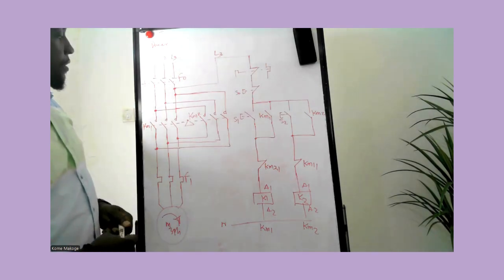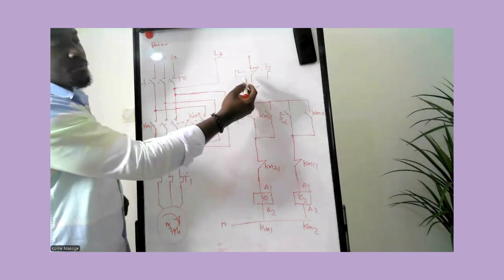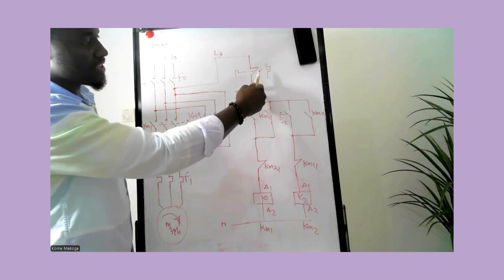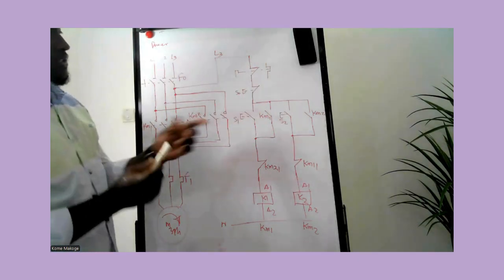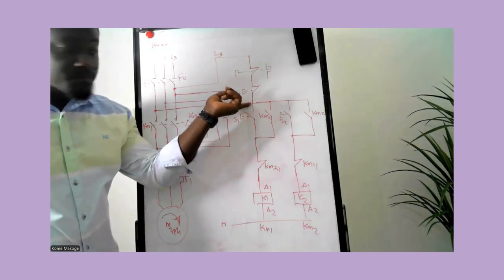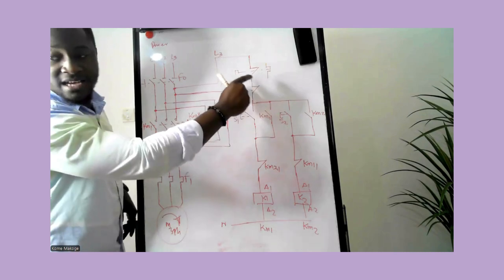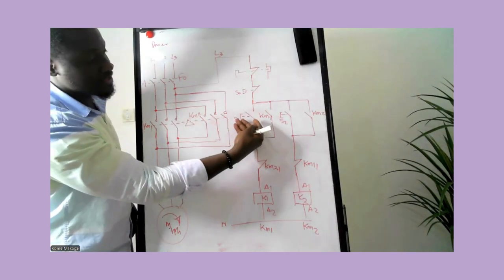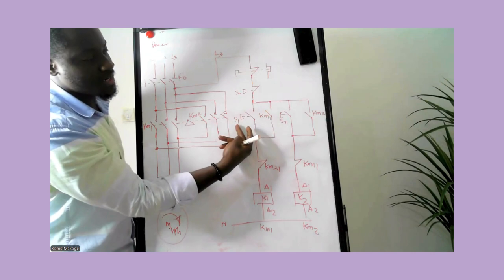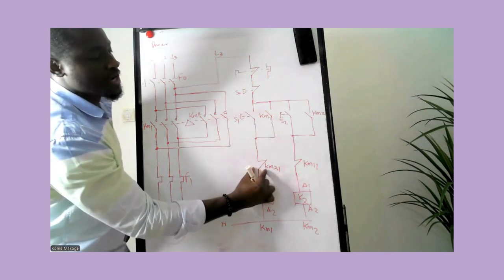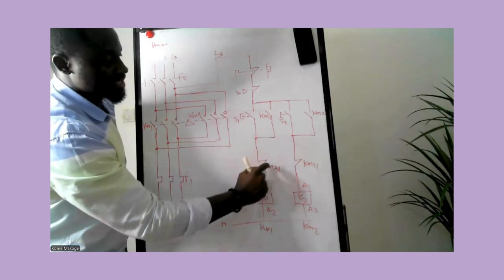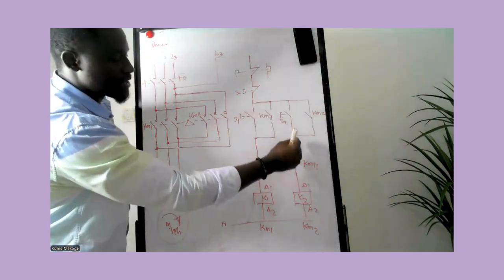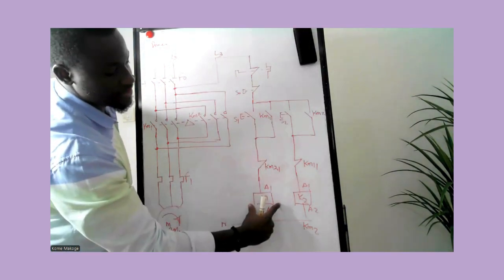We start from the top — this is our thermal relay, the same as we had on the direct online starter. The next is a close contact which is the stop push button, represented as a close contact. Next is the start push button, represented as an open contact which is S1, and then we have a close contact of KM2. As we continue I'll explain why we use the close contact of KM2.